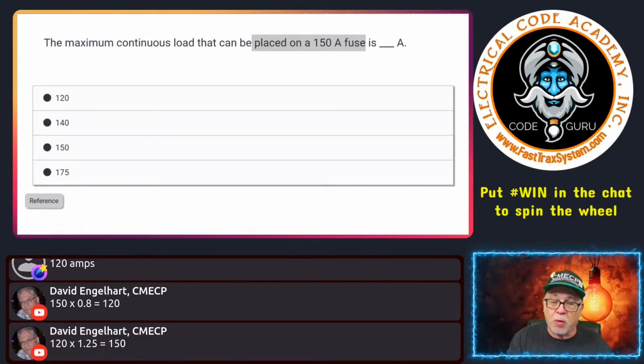Whether it's three hours or more at its maximum output, or the code says it's a continuous load, it's a continuous load. But that's the value. For sizing conductors, we take that value and do it at 125%. That is to size the wire for a continuous load, but it also correlates with the breaker, because the typical breaker is going to be limited for continuous load to 80% of its value.